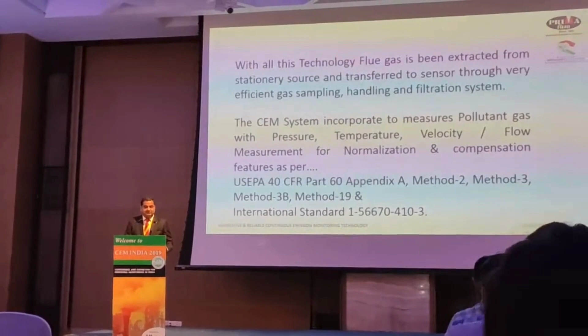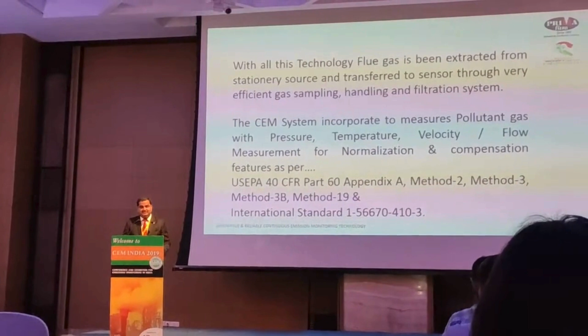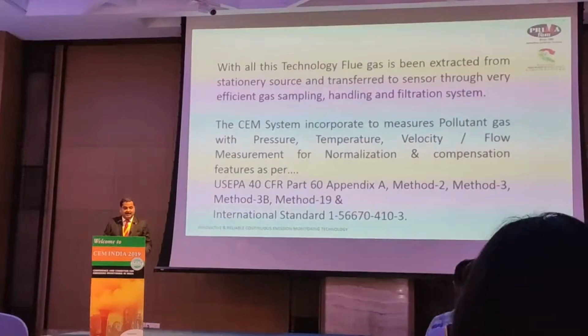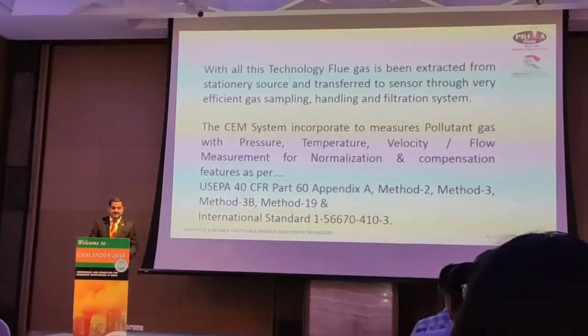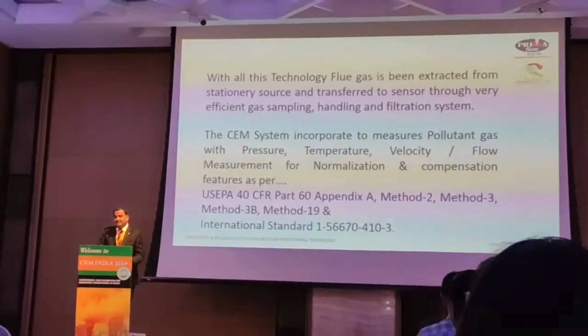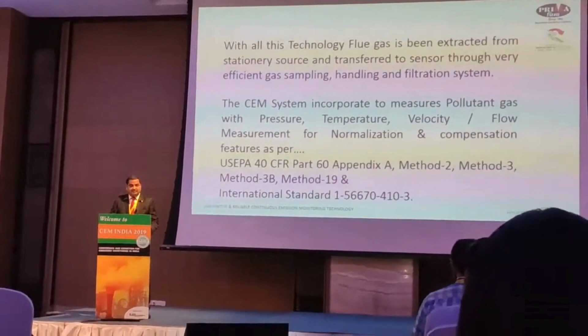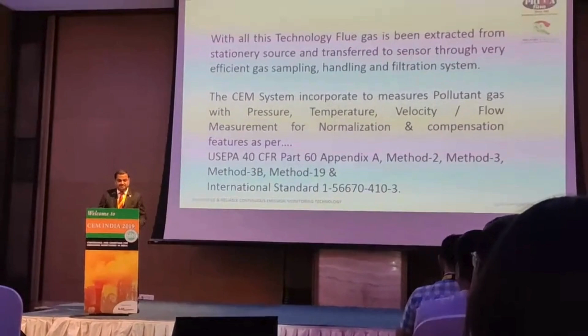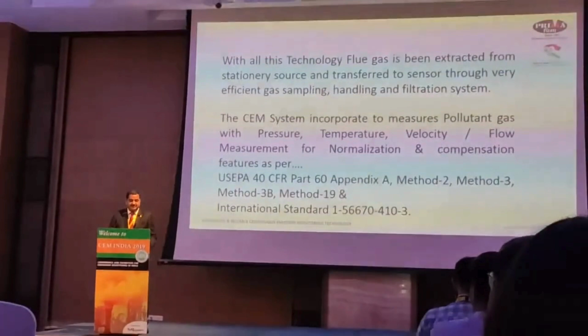With all this technology, flue gas is being extracted. So we have done the entire analysis on extraction-based technology, with gas handling and transfer to the sensor through a very efficient gas sampling, handling, and filtration system. As I told earlier, the handling system is the most important part in the CEMS. Furthermore, while doing all this analysis, we have incorporated pollutant gas measurement with pressure, temperature, velocity, and flow measurement for normalization and compensation features.